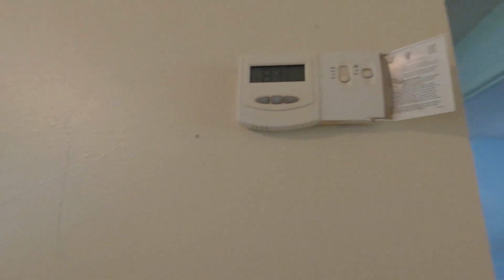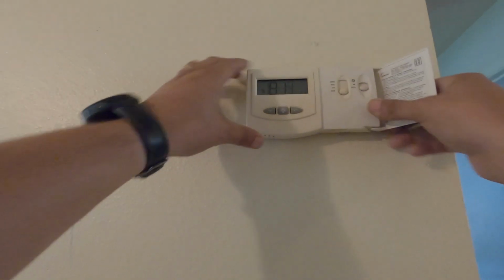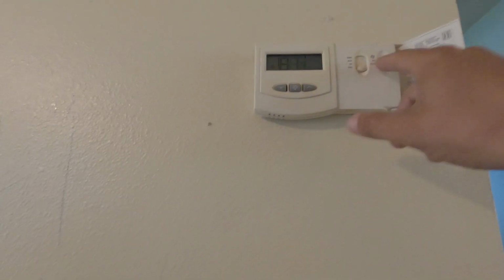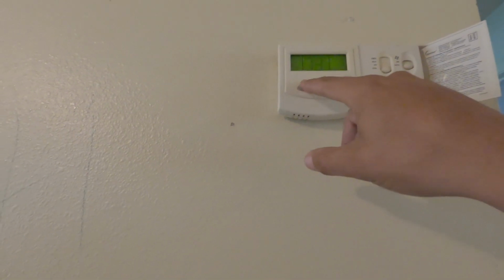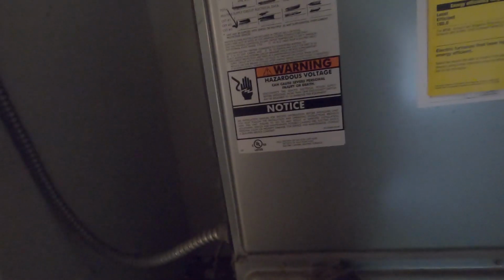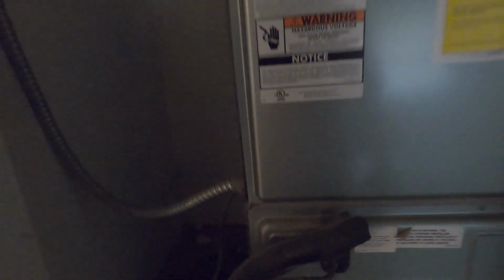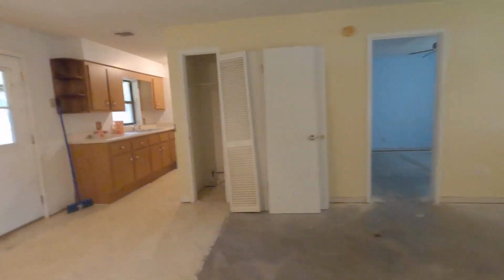So let's go to our thermostat here. Robertshaw. These thermostats are garbage, but it is in cooling. Fan is in auto, and it's set for 72 degrees. So the condenser should be running, and it is not running. So let's head outside and see what we got outside and see why the condenser is not running.